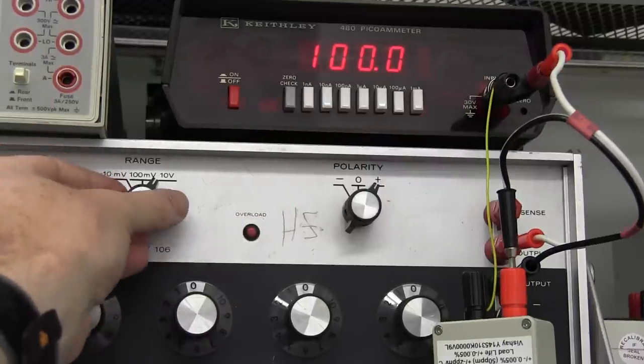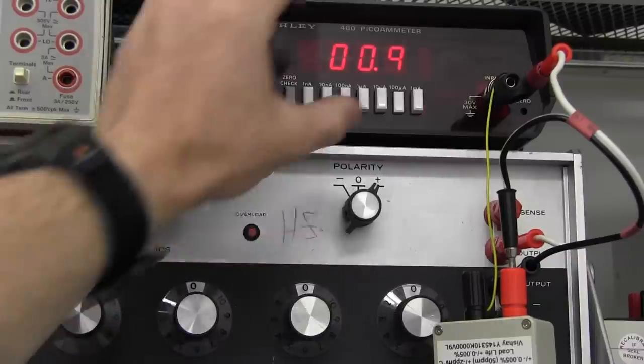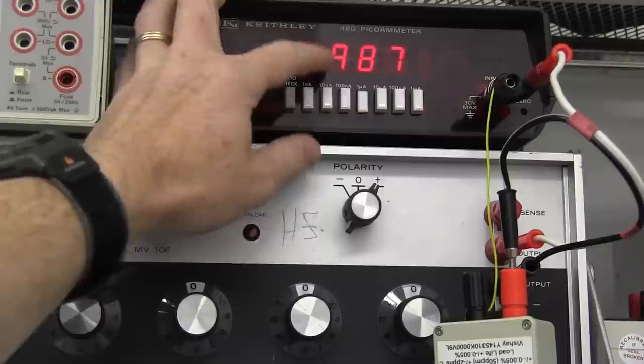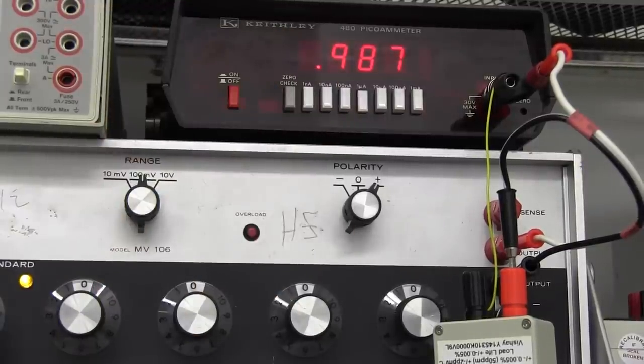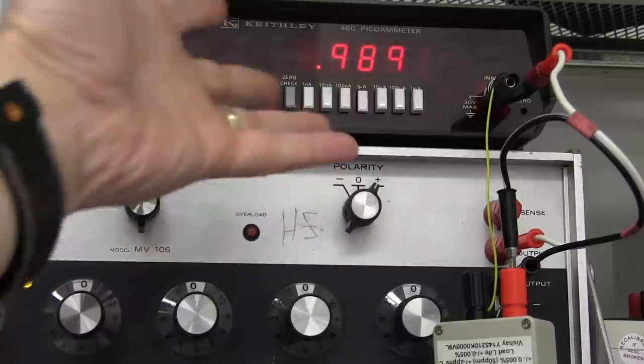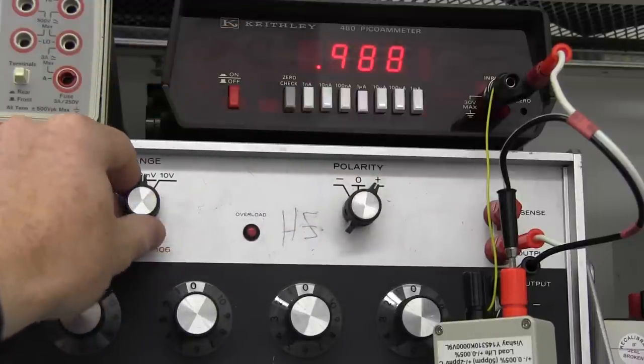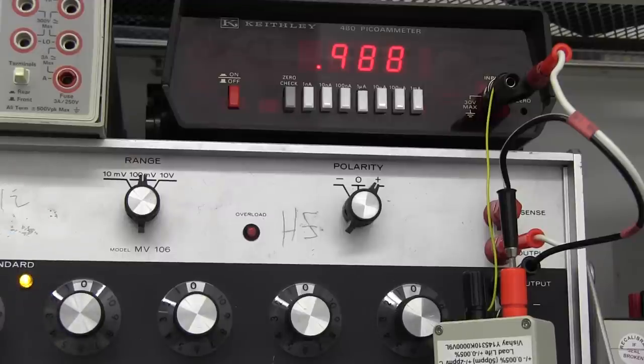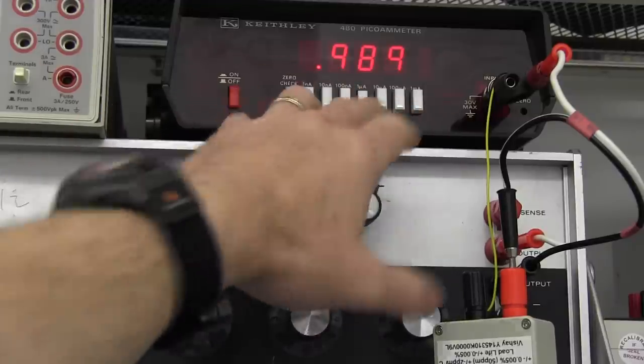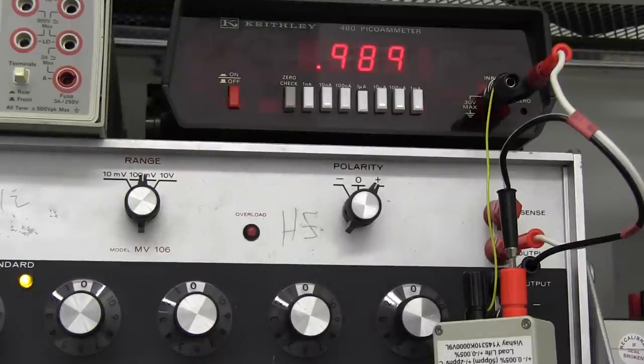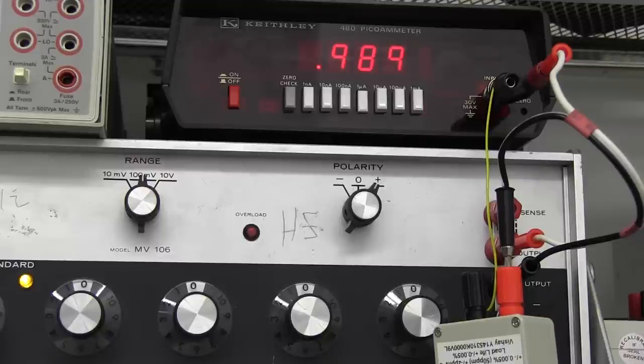Now, you might think that we're simply able to reduce the voltage here and measure the lower current ranges, but that's not really the case. You can see it's slightly out here. So I've got 10 millivolts there over my 10K, which is going to be 1 microamp there, and you can see we're out. But I know it's not out. It's because the burden offset voltage in this thing becomes a very significant proportion of our calibration setup here. So that's why the manual for this thing will recommend minimum input impedances for these various ranges. But what that essentially translates to is not necessarily a minimum input source impedance, but a minimum input voltage, so that the burden voltage of this thing doesn't matter.